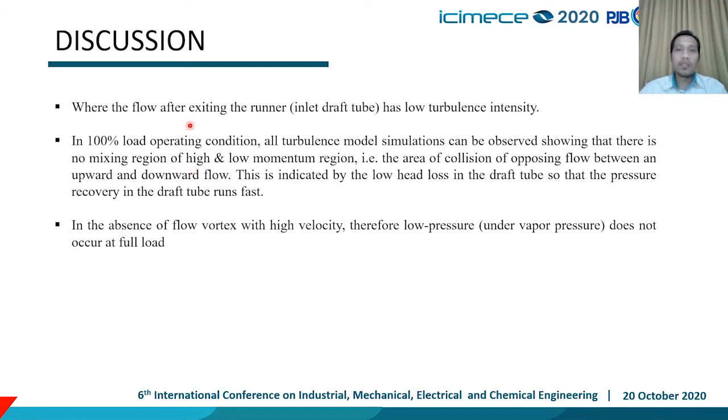The discussion about velocity factor on 100% load is where the flow after exiting the runner inlet draft tube has low turbulent intensity. In 100% load operating condition, all turbulent model simulations show that there is no mixing region of high and low momentum region. This is indicated by the low head loss in the draft tube, so that the pressure recovery in the draft tube runs fast. In the absence of flow vortex high velocity, low pressure under vapor pressure does not occur at full load.